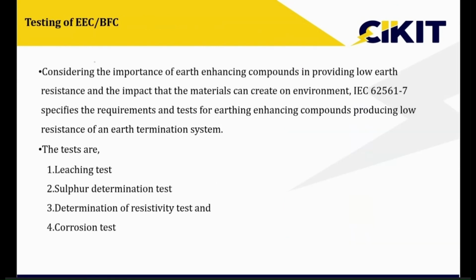electrode, so that it protects the earth electrode from the corrosion. Since we are directly dumping it on the soil, the standard has explained about 4 different testings that are required for this particular compound. So we need to ensure that the compound is completely tested before using it.